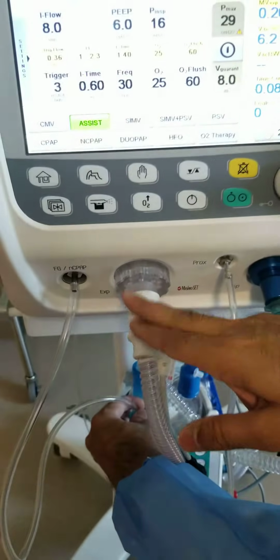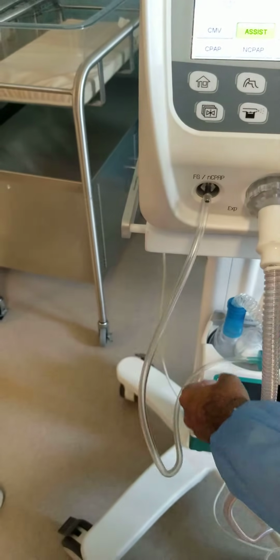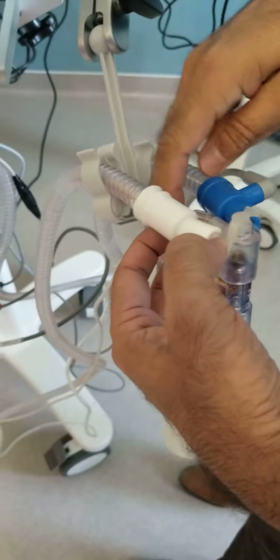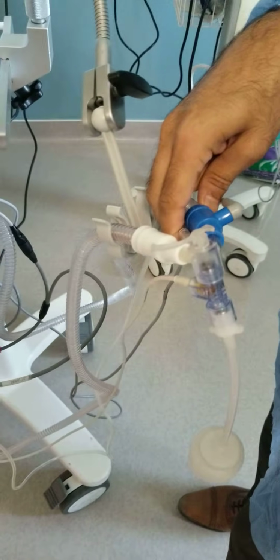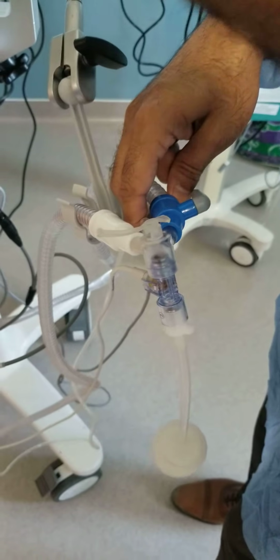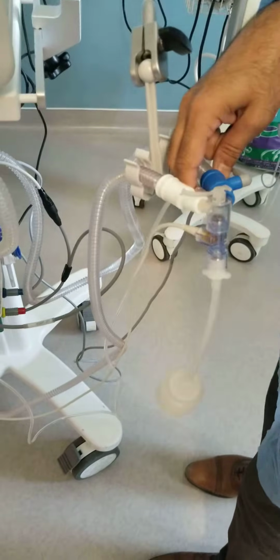So I'm just using this one, and I'm using the pressure, I will not even use this. The only difference is I have the same circuit, I will put my flow generator between these two. So with the same circuit you can use conventional ventilation, and then while weaning off, you can connect the generator and change.